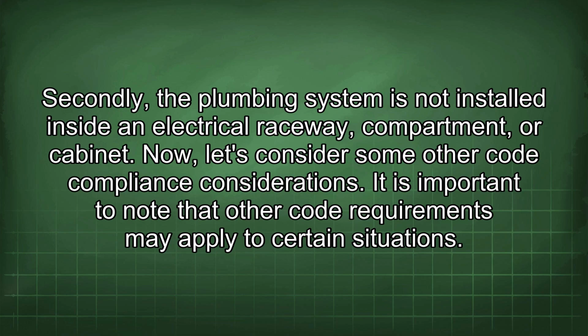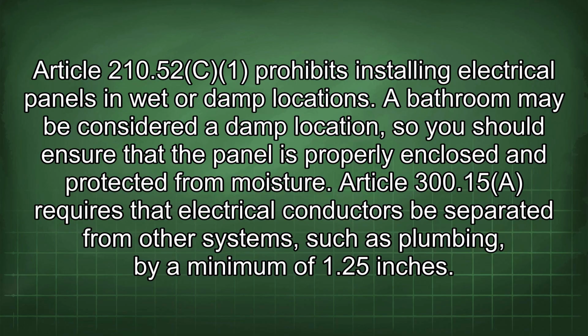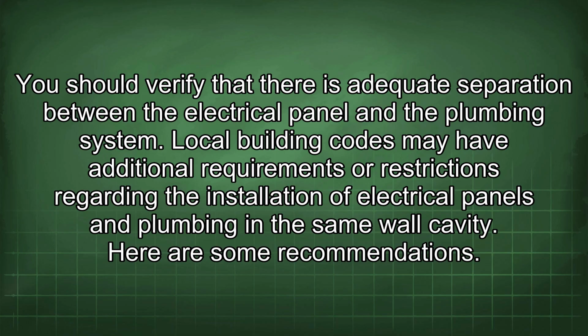Now, let's consider some other code compliance considerations. It is important to note that other code requirements may apply to certain situations. Article 210.52 code prohibits installing electrical panels in wet or damp locations. A bathroom may be considered a damp location, so you should ensure that the panel is properly enclosed and protected from moisture. Article 300.15 requires that electrical conductors be separated from other systems, such as plumbing, by a minimum of 1.25 inches. You should verify that there is adequate separation between the electrical panel and the plumbing system.